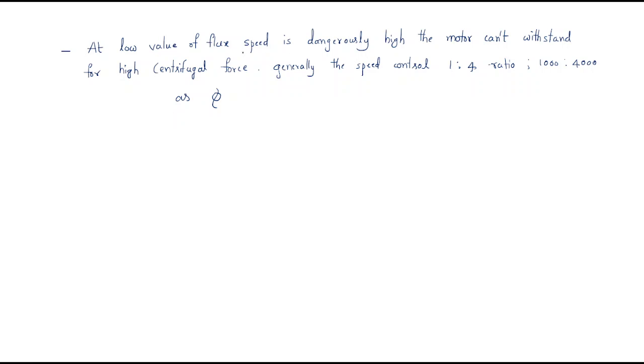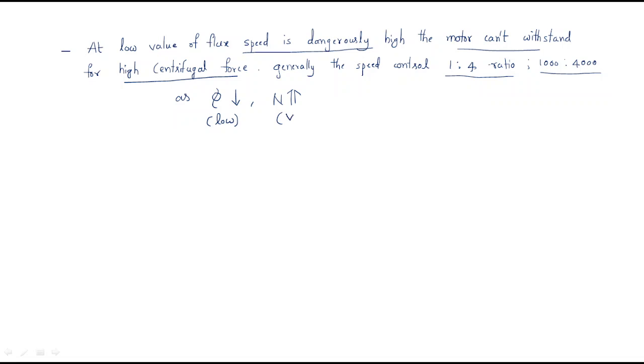At a very low value of flux, the speed becomes dangerously high and the motor cannot withstand the high centrifugal force. Generally the speed control ratio is about 1:4, such as 1000 to 4000 RPM. If flux decreases to a very low value, the speed becomes very high, causing more centrifugal force on the rotor which can damage it. Also, when flux decreases, torque also decreases because torque is proportional to flux multiplied by armature current.